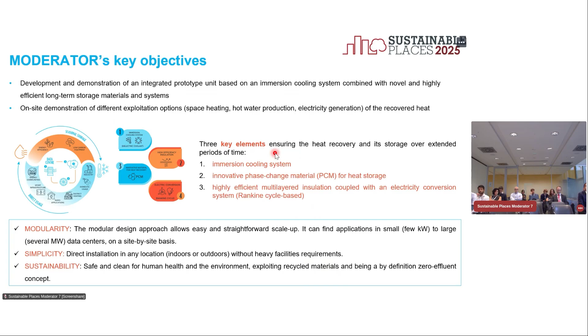Quickly looking at the consortium, we are distributed all around Europe. One of the planned pilots is in Greece. Our data center provider, who also developed their own immersion cooling system, is Synapsicom, located in Athens, which is where our first pilot will be built. HSLU and COBA work together on developing the phase change material and the storage system itself, meaning how to get heat in and out of the materials. Sintef in Norway is doing simulation work on the temperature distribution in the immersion cooling unit, looking at how temperature affects the server and how we can achieve as high a temperature as possible in the dielectric fluid.